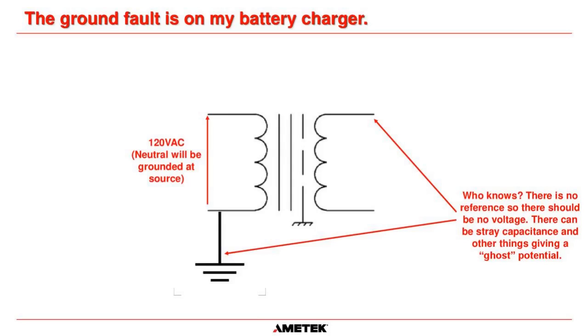What you can do is, if you can figure out roughly when it happens, you could turn your charger off and allow the batteries to supply the load. Open the output breaker from the charger, and then measure the voltage from positive to ground and negative to ground with a Fluke. When the fault happens, you can see it on your Fluke, that there is a ground. And if it still happens when you've isolated the charger, then you know it's something on either your battery or your load circuits. But I don't envy anybody that has to find an intermittent fault like that.